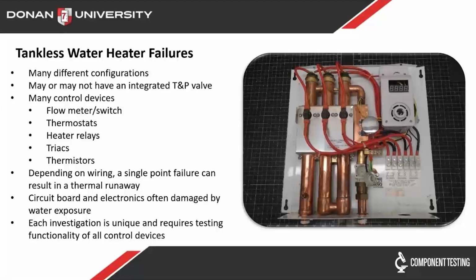And again, depending on how much the manufacturer has invested in redundancy or thought through the various failures of the water heater, you can get single point failures or sometimes even combinations of failures together that can result in thermal runaways. I've seen it on multiple water heaters. I think the takeaway is that each of these investigations is unique. Since there's so many constructions, I haven't really seen any trends of failures on these. There's one related to flow sensors, but other than that, it's kind of an individual puzzle that you have to go through for each one.